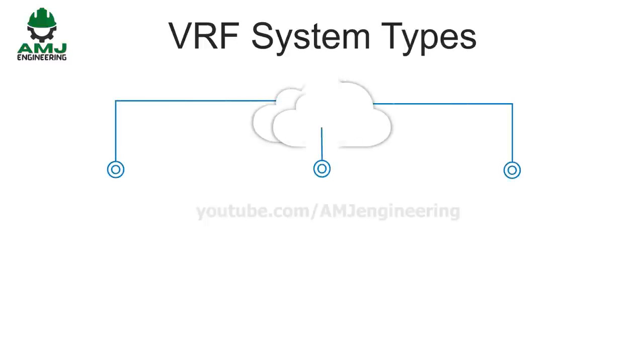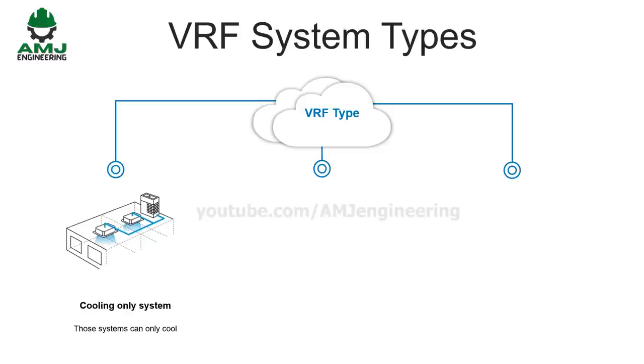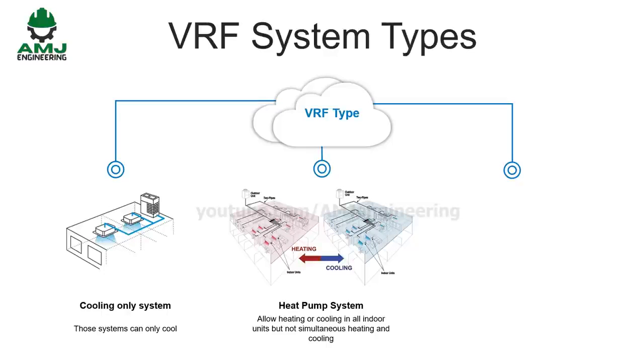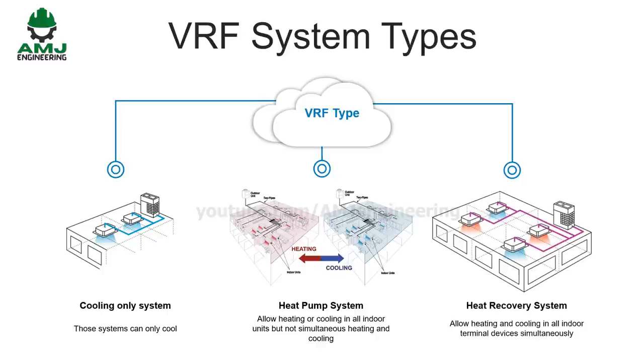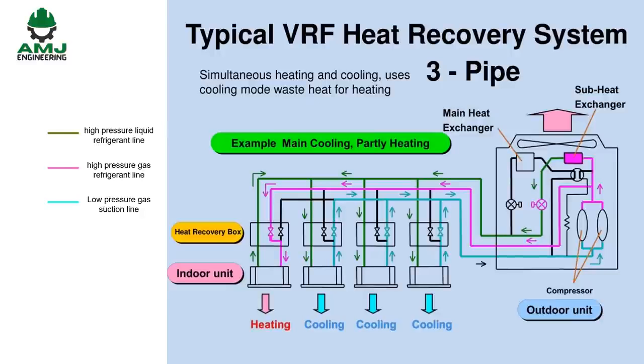There are 3 VRF system types. Cooling-only systems. Those systems can only cool. Heating is not available. Heat pump systems, also known as two-pipe VRF, allow heating or cooling in all indoor units, but not simultaneous heating and cooling. All the indoor units can either heat or cool, but not at the same time. Heat recovery systems, also known as three-pipe VRF, allow heating and cooling in all indoor terminal devices simultaneously. Those systems are the most sophisticated ones. Let us see how a VRF heat recovery system works.